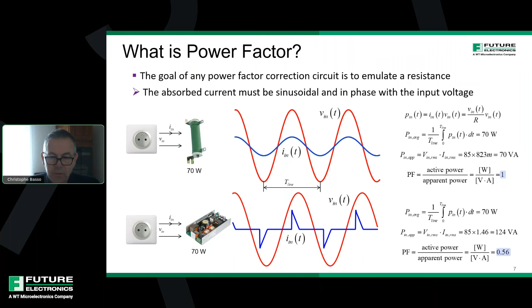A power factor less than unity induces a larger circulating RMS current for a given active power, as we saw in the previous example. Imagine an AC outlet whose maximum RMS current is limited to 15 amps. You could only connect 3 250-watt workstations in that example.